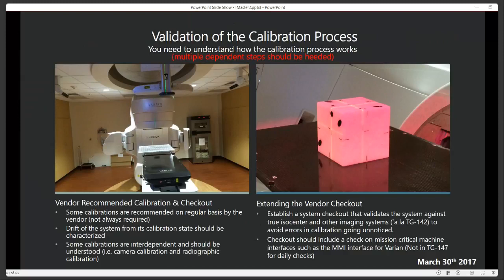So, validation of the calibration process. The vendors have recommended calibrations and checkouts. No matter what vendor you have, you have to calibrate a vision system to the geometry of the room. What you see there on the left is a plate that lays on the table at IsoCenter, and you use it as a monthly calibration, as Vision RT calls it for their cameras, but it is a calibration that you need to check to see if you drift away from. It is called monthly calibration. They have put a time or temporal name on it, so you would think you'd have to do it monthly.